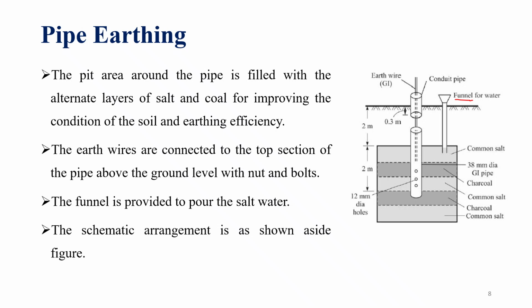The advantage of pipe earthing as compared to plate earthing is that we connect the earth wire to the electrode near the ground level, above the ground level, so that we can identify whether the earth wire is connected to the earth electrode or not. So periodically you can check that connection. If there is any wrong connection, or if any connection is broken, you can make the reconnection. But it's not possible with plate earthing.